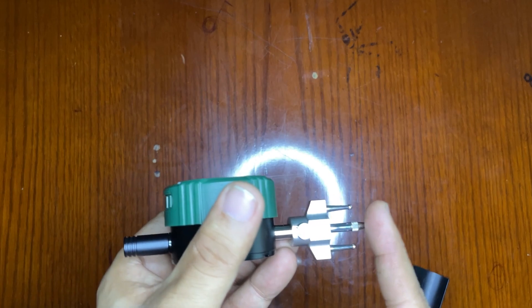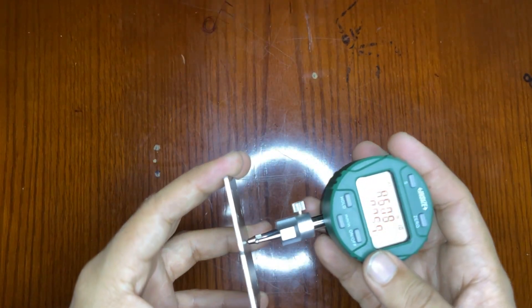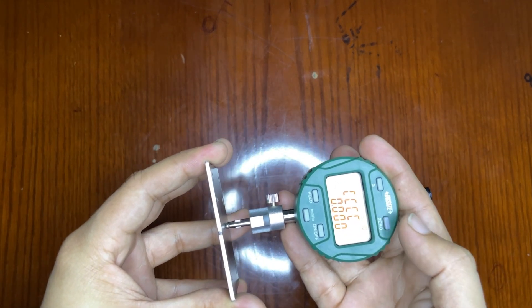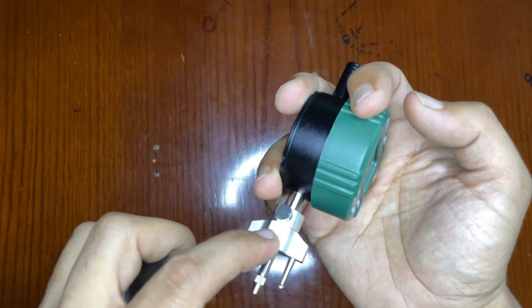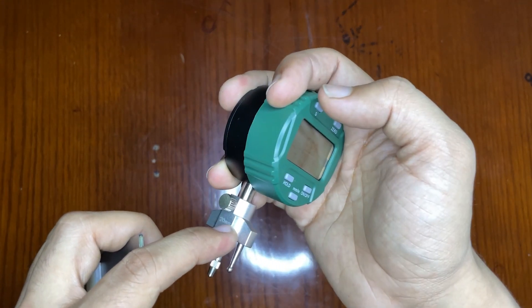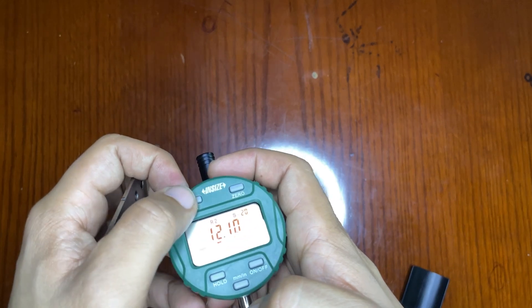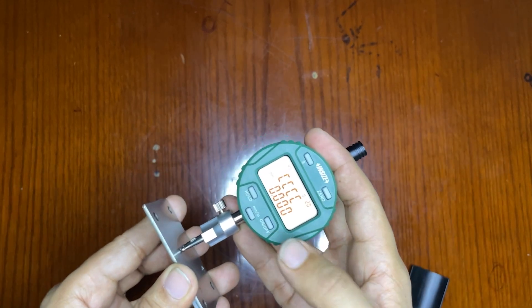Let's start this up. Three points in parallel. First we have to calibrate. We have to take a flat surface. Yeah, you can see here the three points are in line on the flat surface. I can see that easily here. That's why we set it at 90 degrees - we can see the three points and at the same time the measurement. Let's do it again. Yeah, three points in the line. Now set to zero.